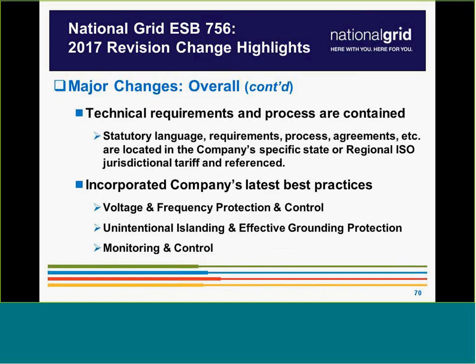We incorporated the company's latest best practices, trying to implement IEEE 1547A. The amendment came out in 2014, and that coincides with what Jim talked about earlier with the ride-through requirements. All of that is permitted by 1547A, but if you're only looking at 1547, it really wasn't necessarily permitted. So we also updated the monitoring control section, the unintentional islanding, and also tried to clarify the effective grounding section.